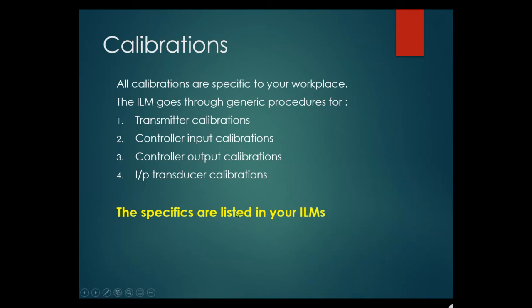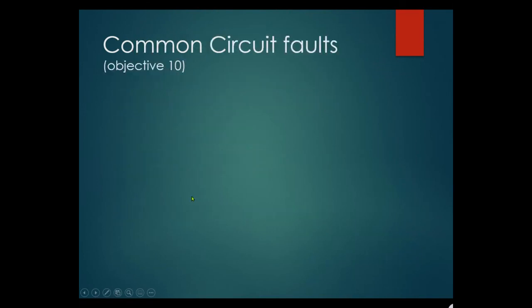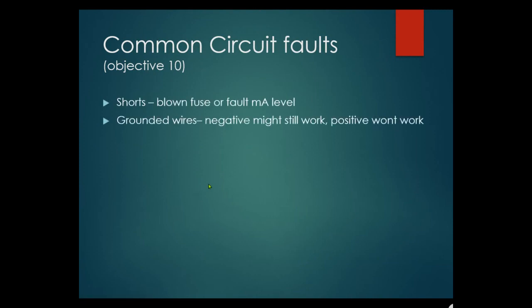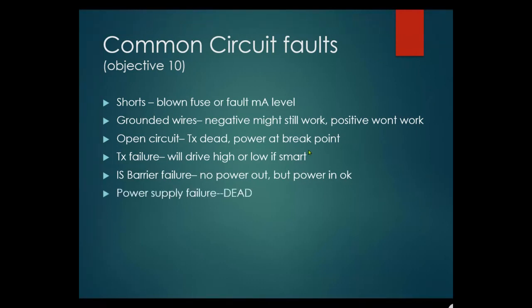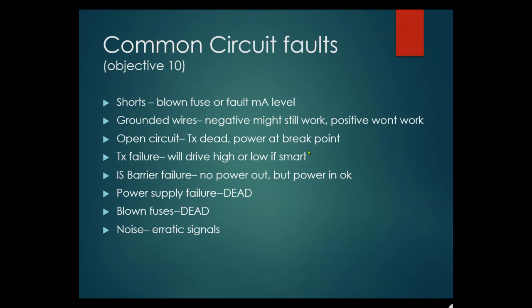Common circuit faults: short circuit — blown fuse or fault milliamp level; grounded wires — negative might still work, positive won't. Open circuit — transmitter is dead, so check power at breakpoint. Transmitter failure — smart transmitters will drive high or low signal. Barrier failure — no power out but power in is okay. Power supply failure — no signal driving the 4 to 20mA transmitter. Blown fuse — dead signal. Noise — erratic signals on the milliamp loop.